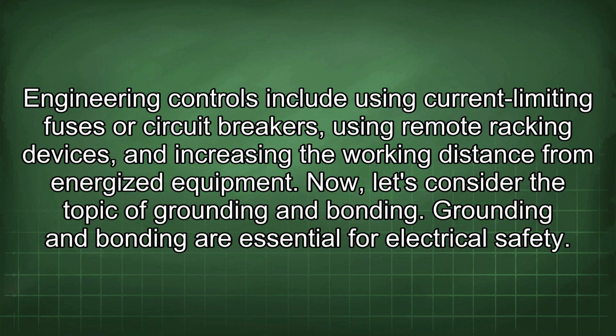Engineering controls include using current-limiting fuses or circuit breakers, using remote racking devices, and increasing the working distance from energized equipment. Now let's consider the topic of grounding and bonding. Grounding and bonding are essential for electrical safety.